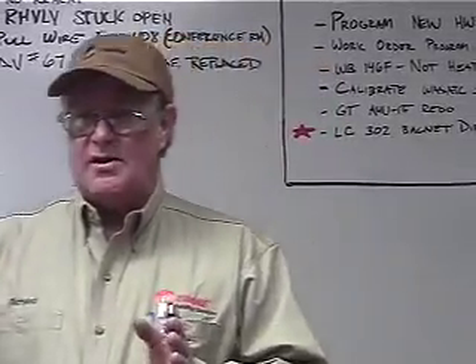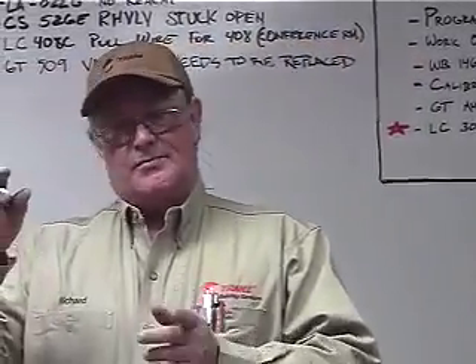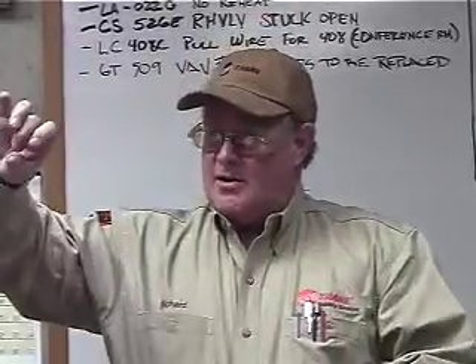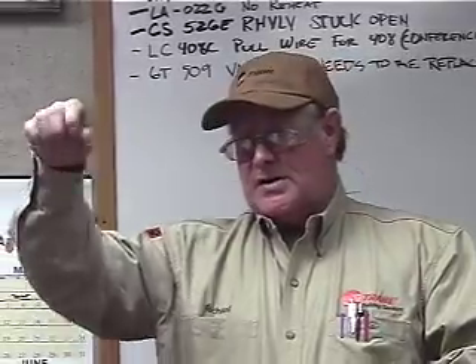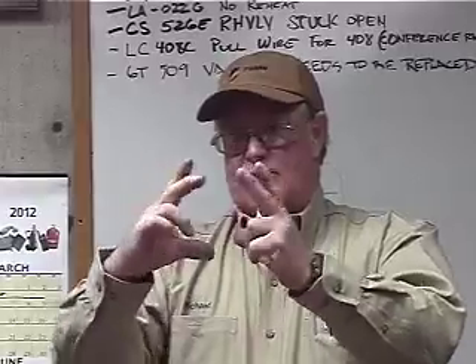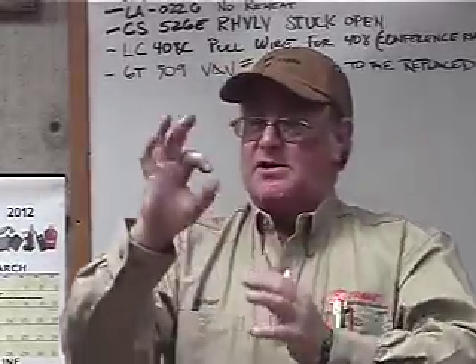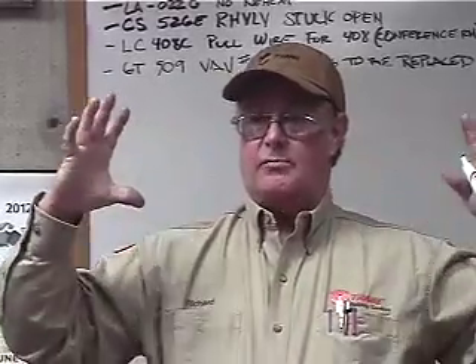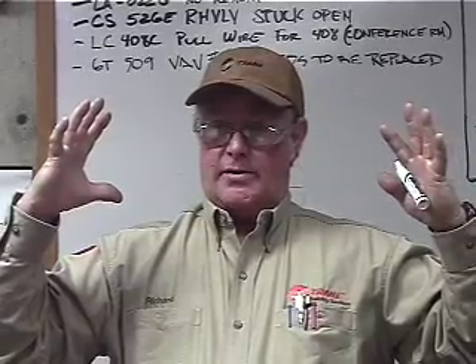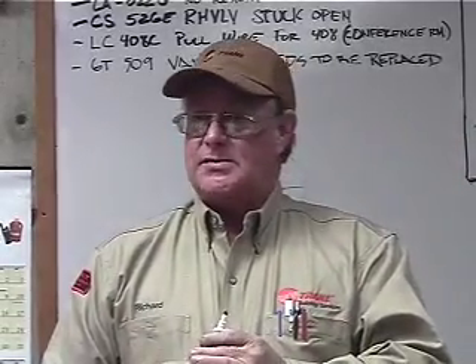It's really hard to describe if you haven't seen what the vanes look like, but like I say, they're just 10 pieces of metal cut in triangles, and on the outside of them there's little knuckles, and as the actuator opens up, those pie-shaped pieces actually open up, and instead of having a small hole like this, you can have a great big hole like this for refrigerant capacity. Yeah, aperture. Right. So that's what we're talking about as far as loading them up.